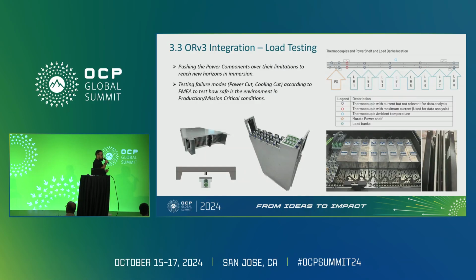This is one of the tests we've been doing, important for understanding that our conceptual information is real. We were questioning whether we can push a power shelf further in immersion, whether every power supply can actually deliver more than it was designed for. The answer is yes. In the test you'll see next, which Amy referred to earlier regarding the FMEA community, it speaks to the density we can achieve. Down on the left you can see a picture with a lot of heat loads, not servers, because they're too expensive if we end up frying them or they fail during testing. So all of those are heat loads generating the load, 54 kilowatts of heat load, and the power shelf on the left is delivering those 54 kilowatts.